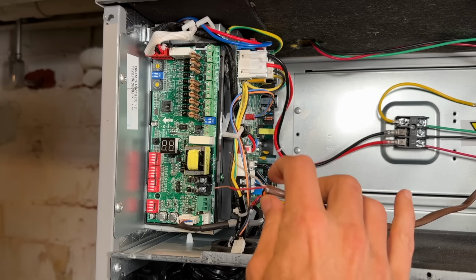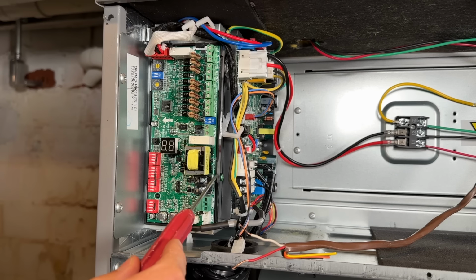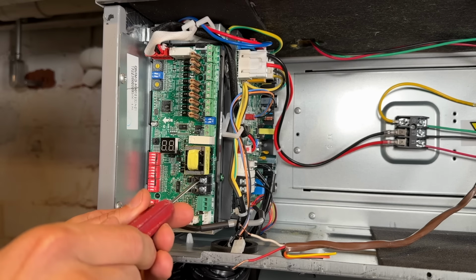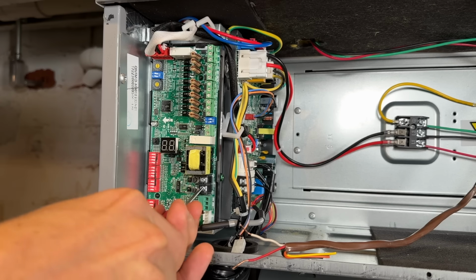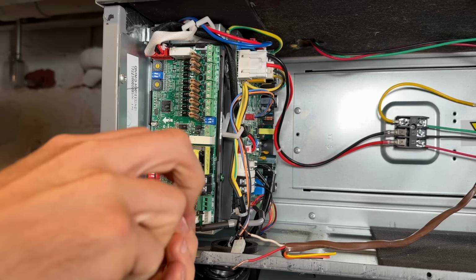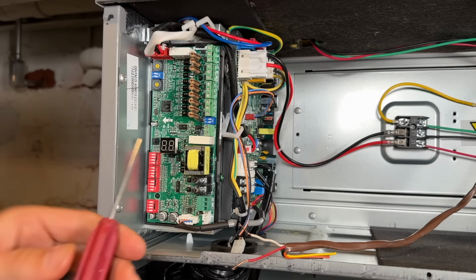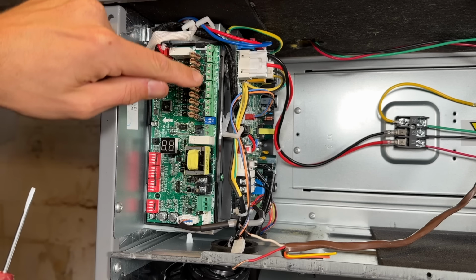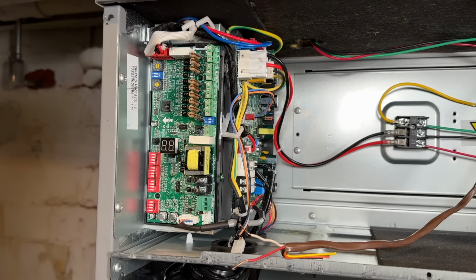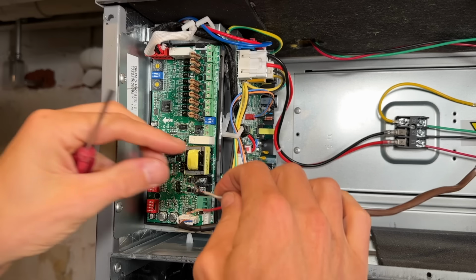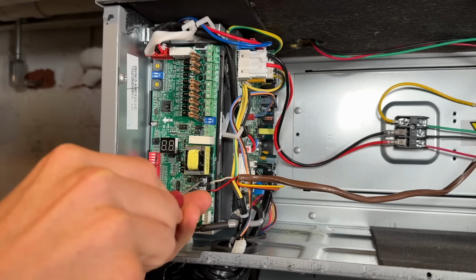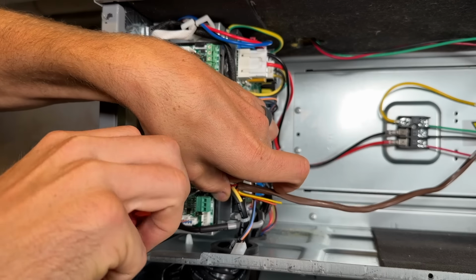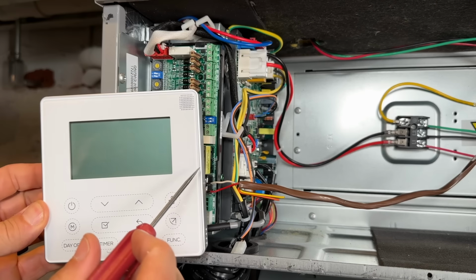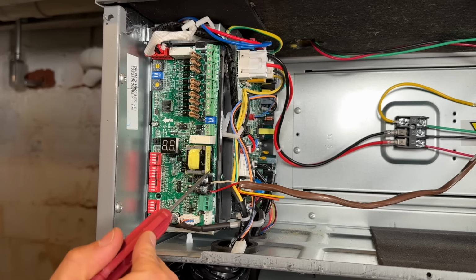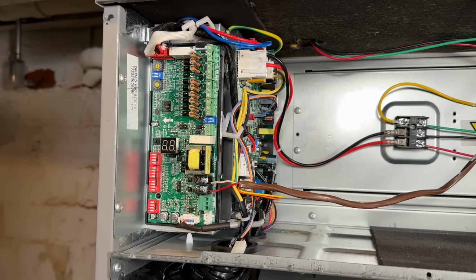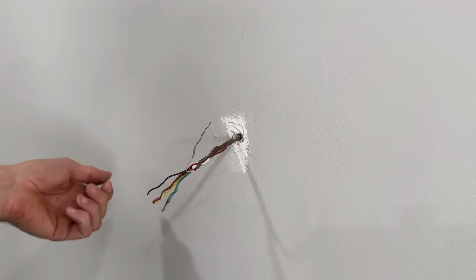Since we are doing only the 2 wires, we're going to be going to HA and HB down here. If you were using a Nest thermostat, you would not be wiring down here. You'd be going off of these terminals here and doing more of a traditional wiring format with many more than just the 2 wires. So then we'll go mount the thermostat and stay consistent, white going to HA and red going to HB. Again, all we're going to need is these 2 wires.